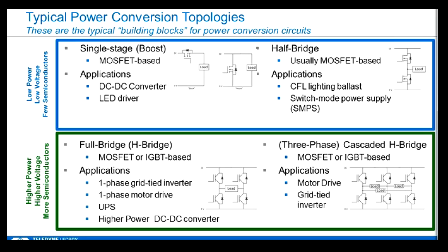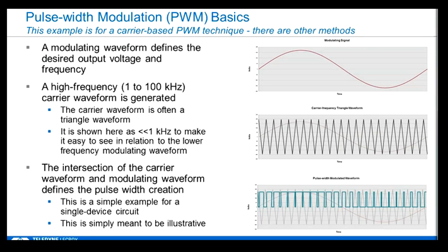And then as you get into what we call a full bridge, it looks like two half bridges in parallel and the load is connected across the midpoint of both. You really could think of this as a single phase bridge. This is the single phase right here. And if you had one more leg, then you get three phases. You have one phase across there, another phase across there, and another phase across there. So by adding two more devices, you go from one to three phase. You increase the capability of the drive or the power conversion circuit a lot, and you don't increase the cost all that much. So three phase is very common on motors especially, and even very small motors, where you might think they don't really have a need for three phase because they're such low power, but they utilize three-phase for control characteristics.